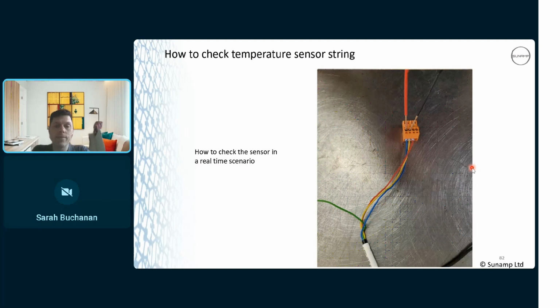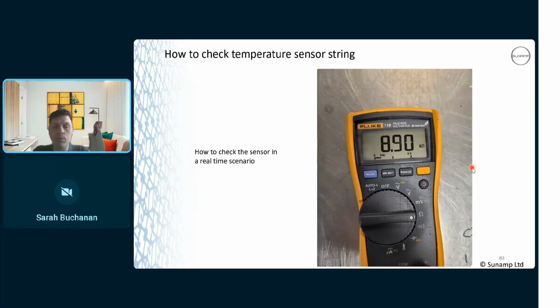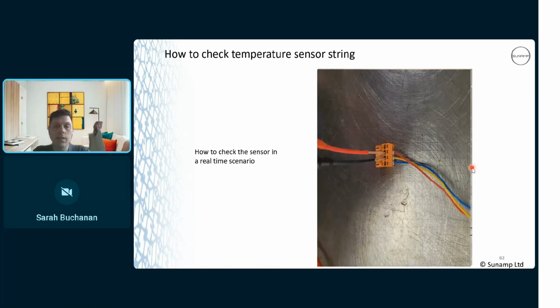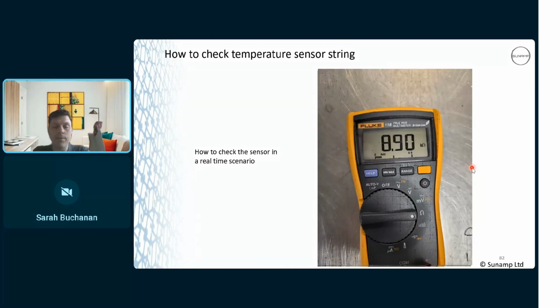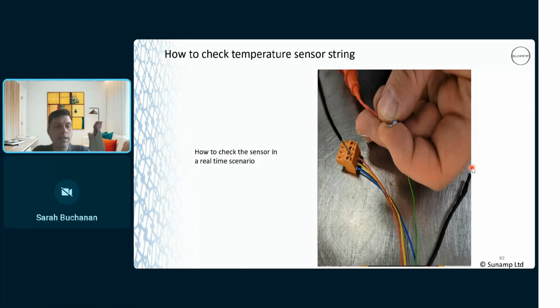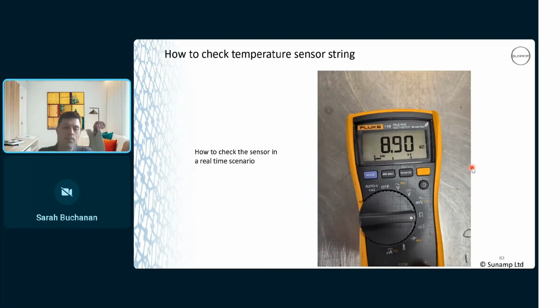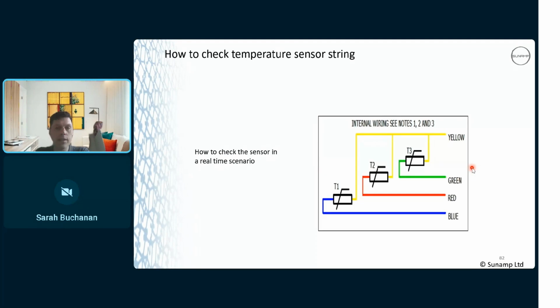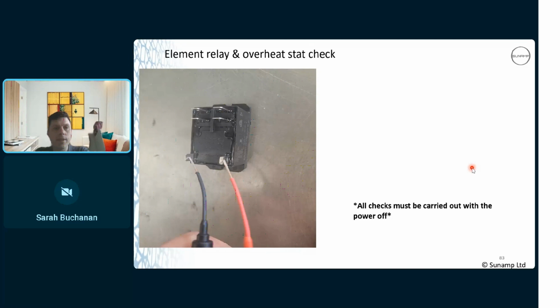How do you check it? This is just a temperature sensor sitting out of a heat battery, but yellow to blue, 8 kilohms. Yellow to red, same. Yellow to green. Does anyone want to tell me what they think the resistance reading is going to be for this? The same, exact same. That's because it was sitting out of a battery in ambient conditions. That's your sensor wire.